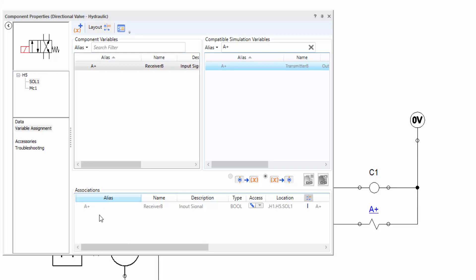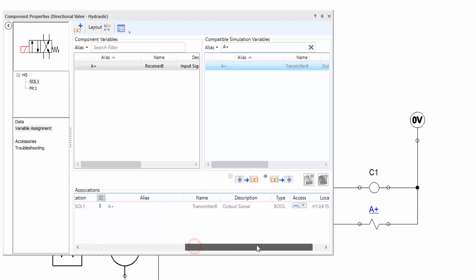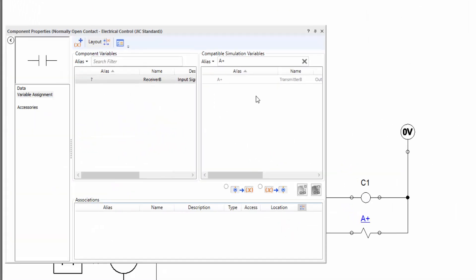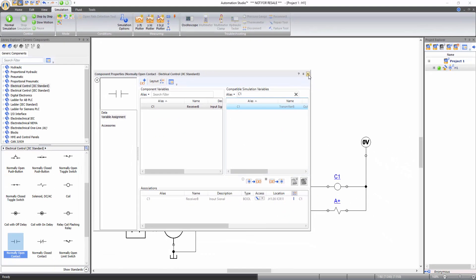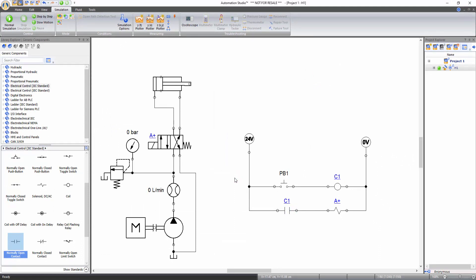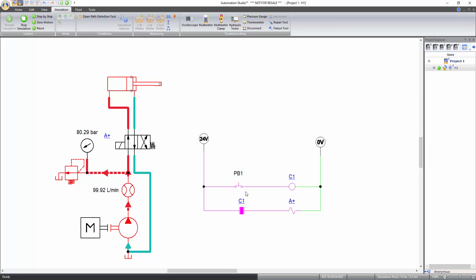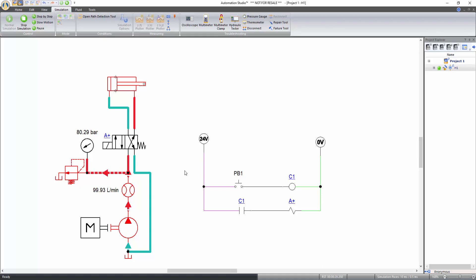You can also see in the association panel that now there is an association between the two components. Similarly, link the normally open contact with the coil C1. Now that the links are made and the aliases are the same between the hydraulic and electrical components, the circuit is ready to be simulated using both technologies. Start the simulation. Click on PB1 and latch it to activate the push button and energize solenoid A+. Observe that the directional valve changes its position and allows flow through the piston end of the cylinder, resulting in its extension. When you click on the push button again, the solenoid is de-energized and the directional valve moves back to its initial position, allowing flow through the rod end of the cylinder, resulting in its retraction. In this way, you can create different hydraulic and electro-hydraulic circuits.